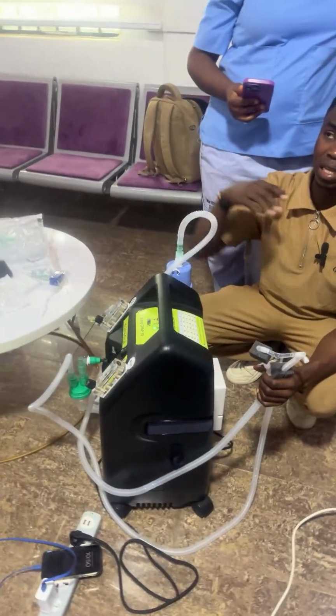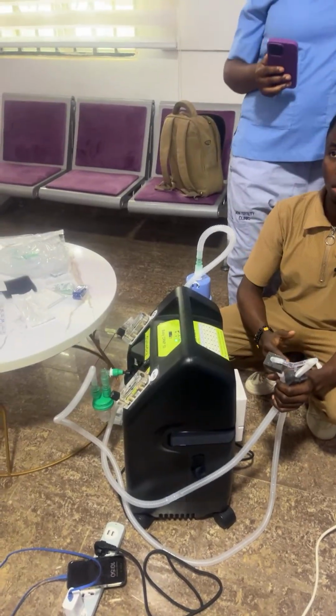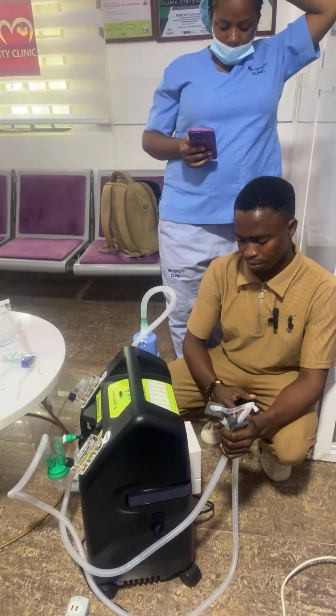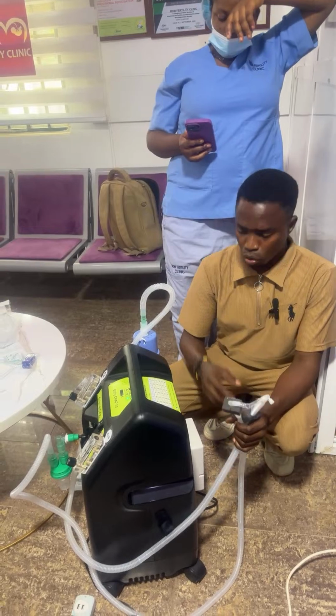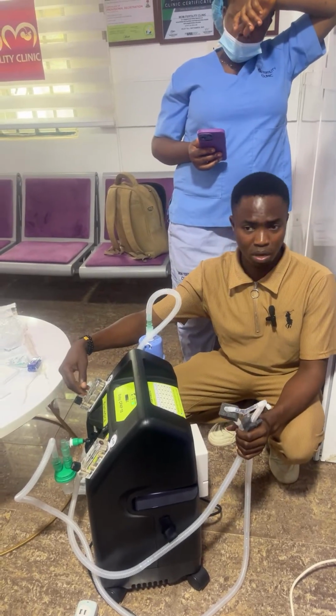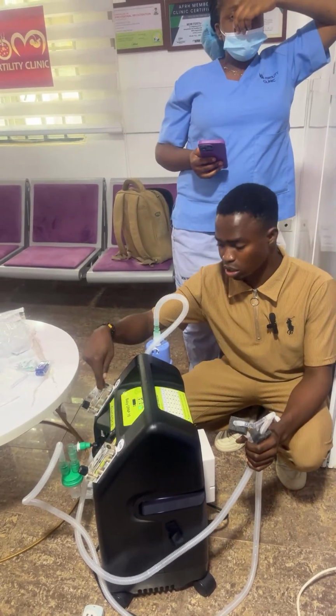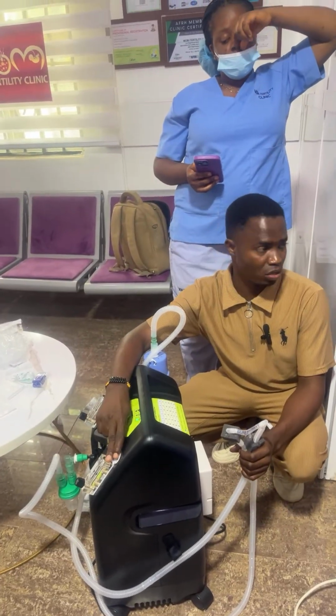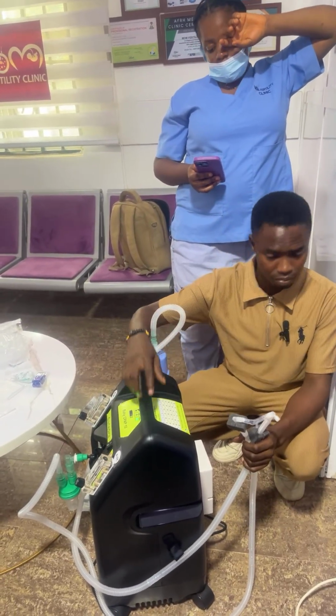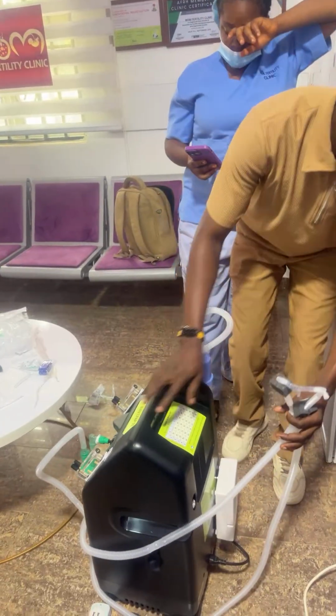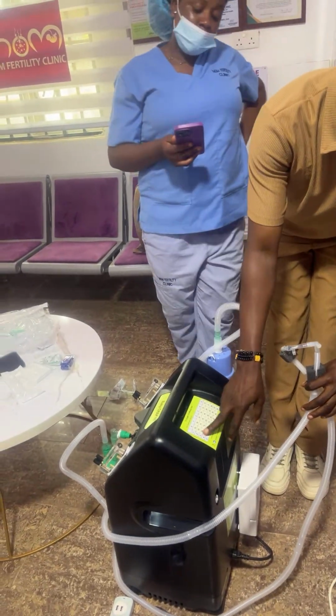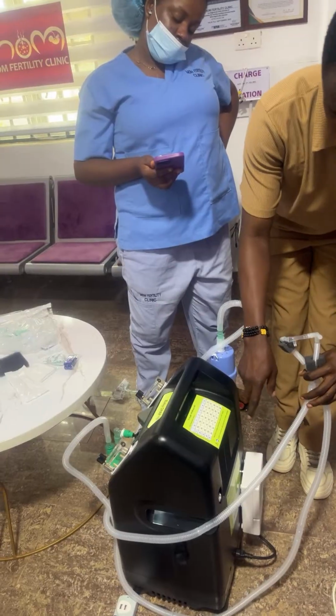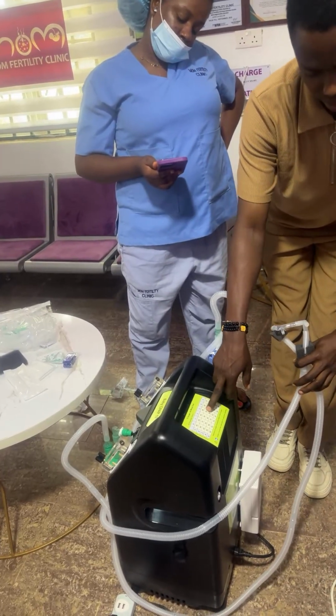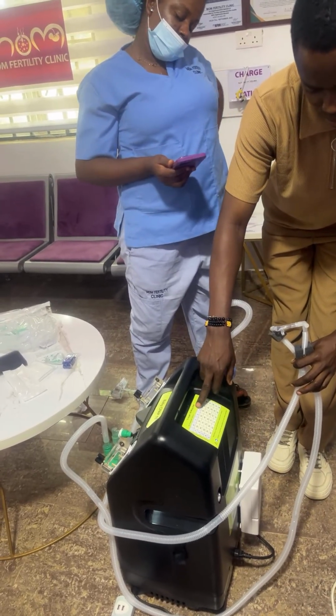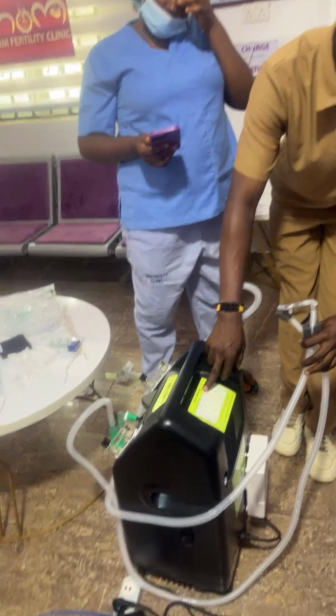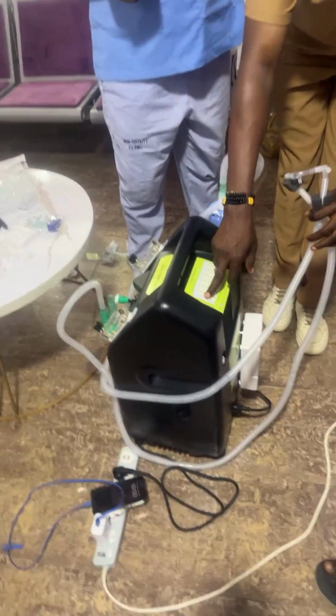Now, let's say there's a patient that requires oxygen FiO2 of, let's say, 50. So you have to set your oxygen to a particular flow rate and air to a particular flow rate to achieve 50. To do that, just come behind here and look for the 50 you want to achieve. Say we have 50 here. That means our air flow rate will be on 3. Oxygen flow rate will be on 2.